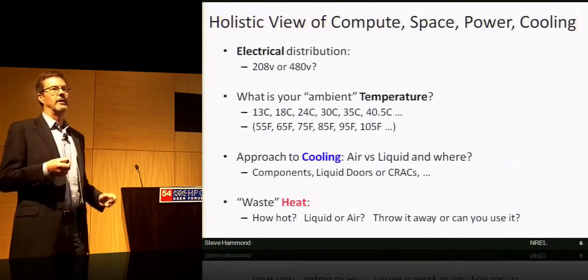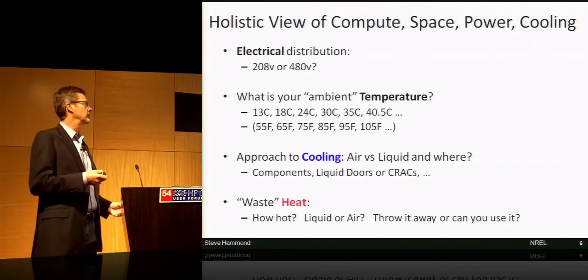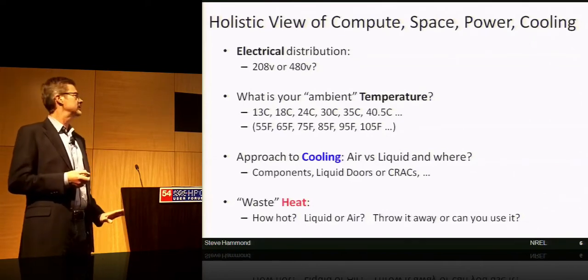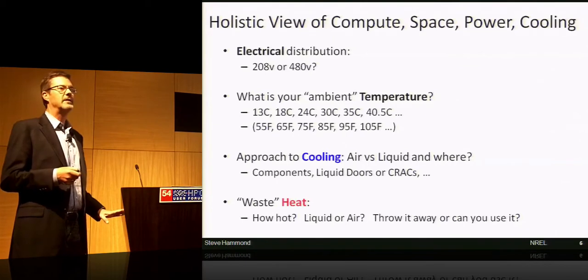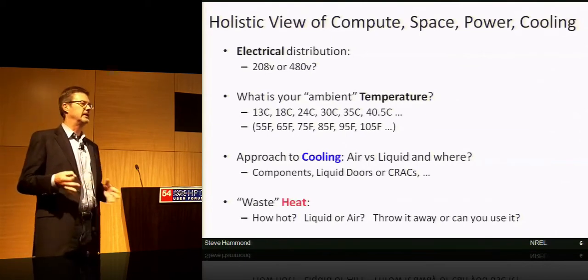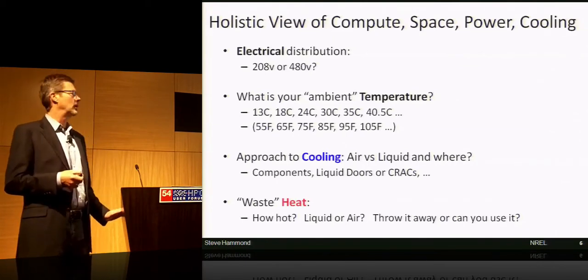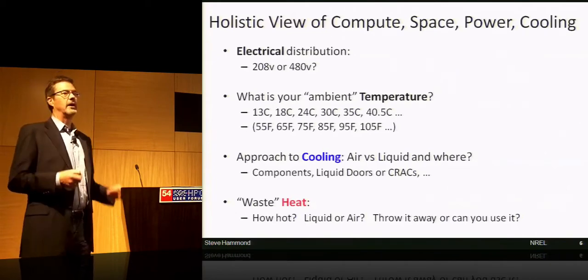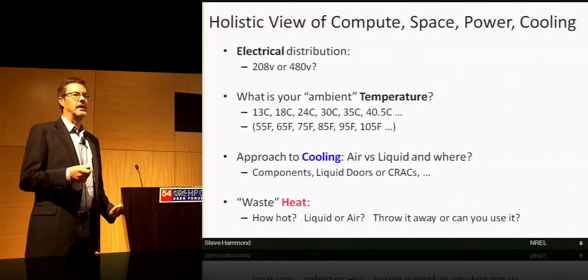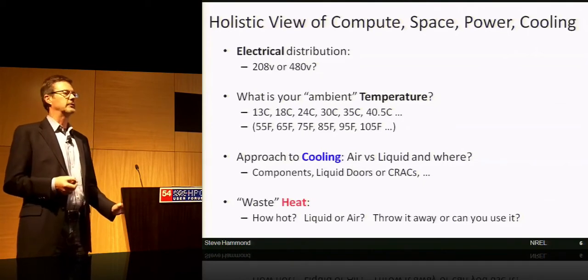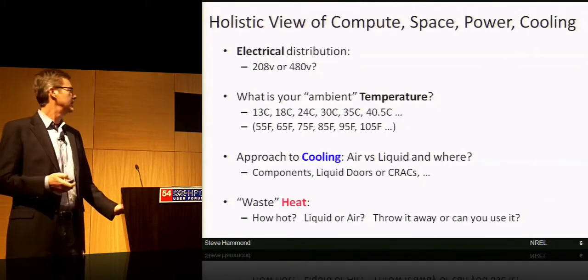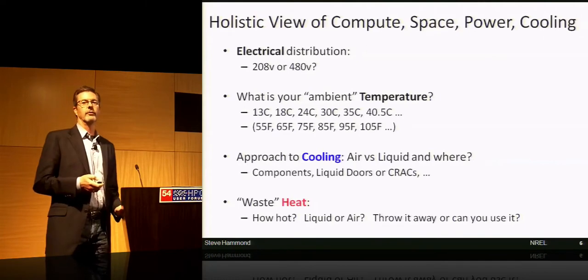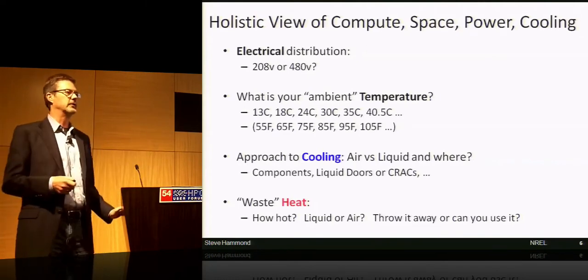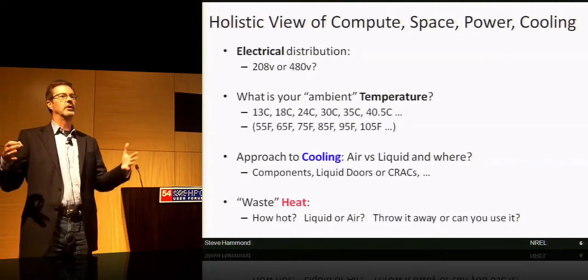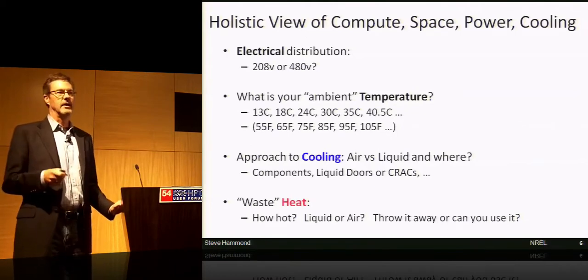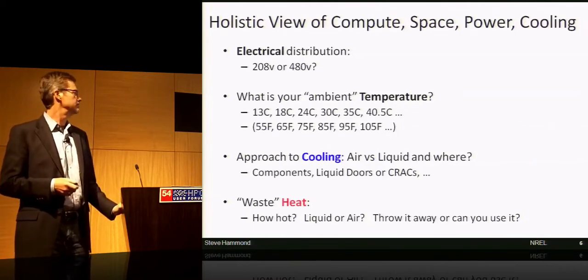Ed had the tray out here from the HP Apollo, showing cooling right at the components. Then for your waste heat, do you declare victory just getting heat to the back of the rack, or carry it further as liquid or air? Certainly 90-degree air has fewer opportunities for reuse than 90-degree water, so do you use it or throw it away? All of these considerations come from a holistic view of the data center as a computing enterprise—look at your whole facility, not just the next system you're buying.